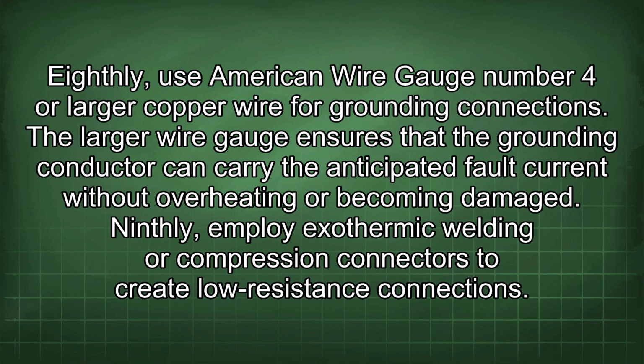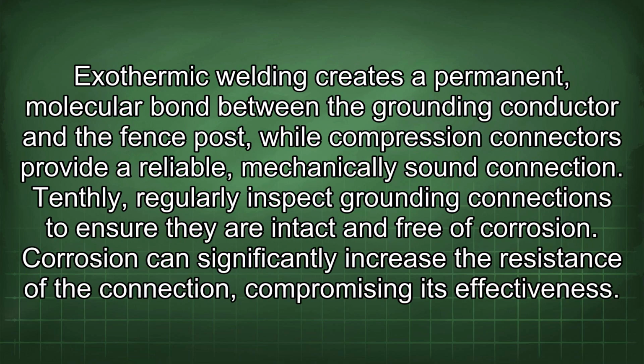Ninthly, employ exothermic welding or compression connectors to create low-resistance connections. Exothermic welding creates a permanent molecular bond between the grounding conductor and the fence post, while compression connectors provide a reliable, mechanically sound connection. Tenthly, regularly inspect grounding connections to ensure they are intact and free of corrosion. Corrosion can significantly increase the resistance of the connection, compromising its effectiveness.